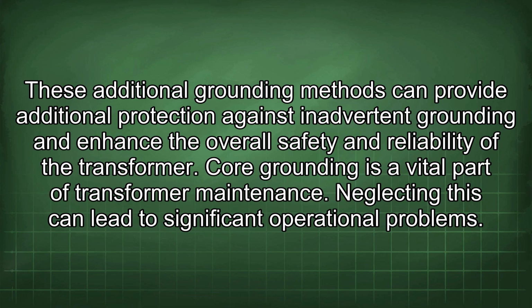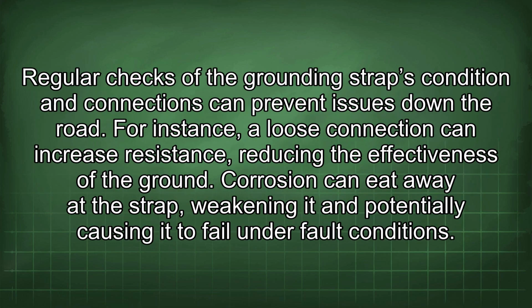Core grounding is a vital part of transformer maintenance. Neglecting this can lead to significant operational problems. Regular checks of the grounding strap's condition and connections can prevent issues down the road. For instance, a loose connection can increase resistance, reducing the effectiveness of the ground. Corrosion can eat away at the strap, weakening it and potentially causing it to fail under fault conditions.